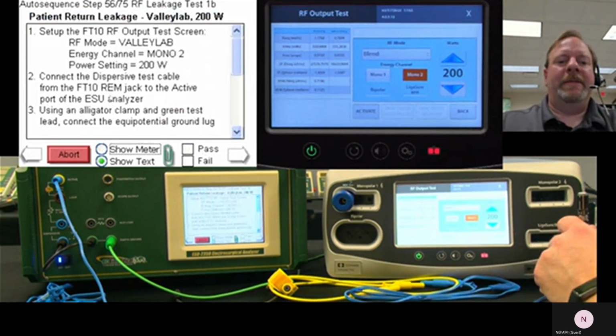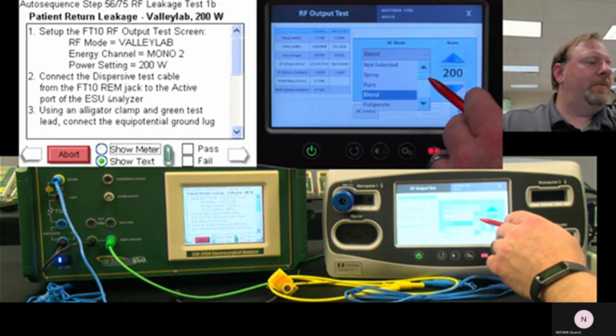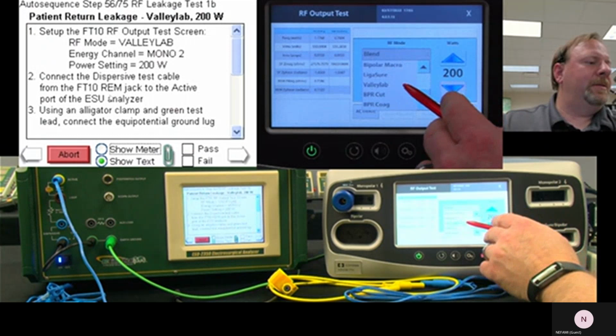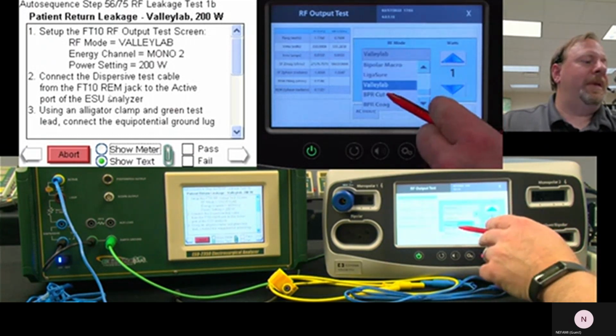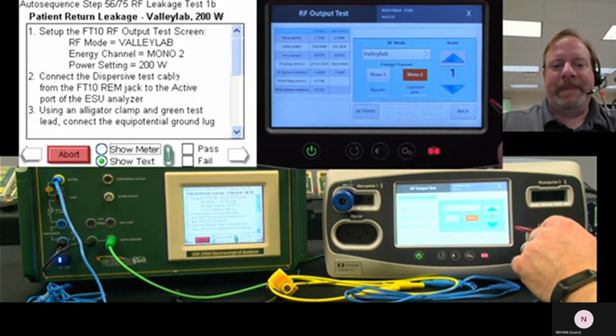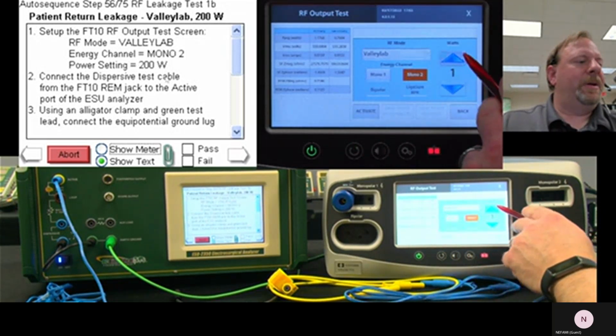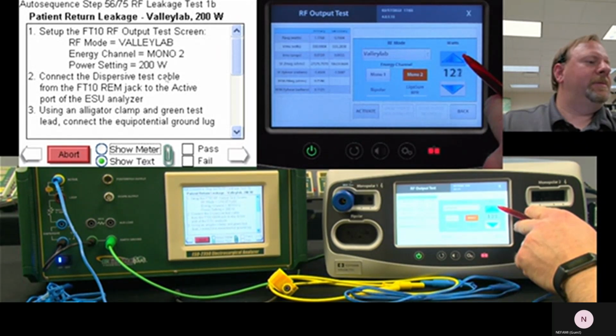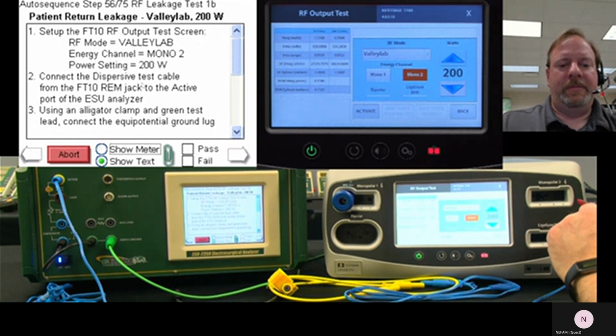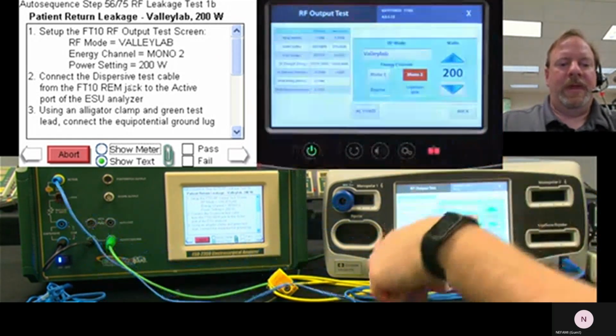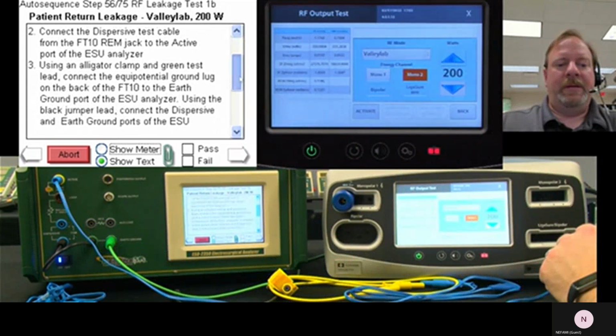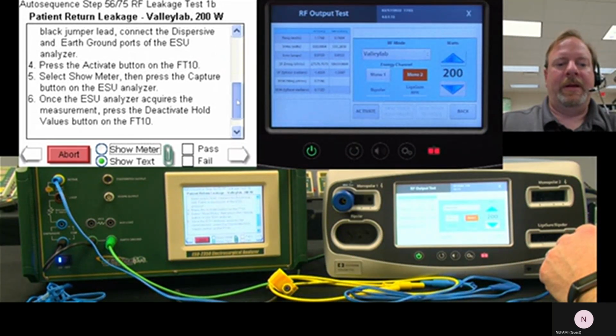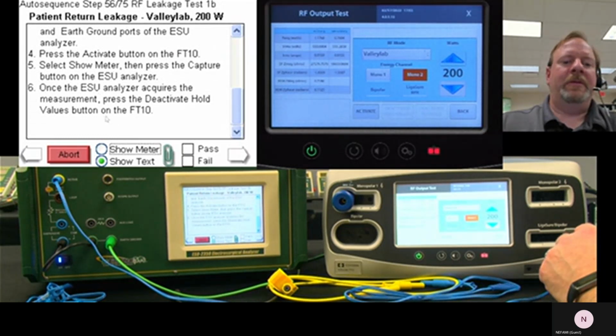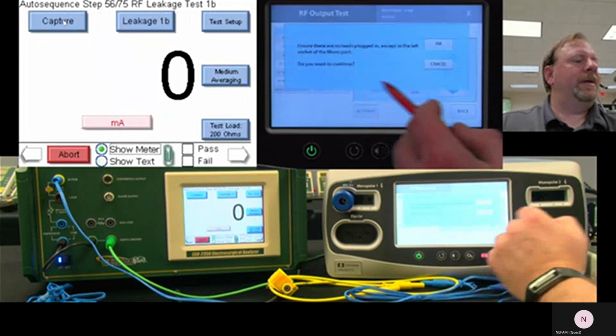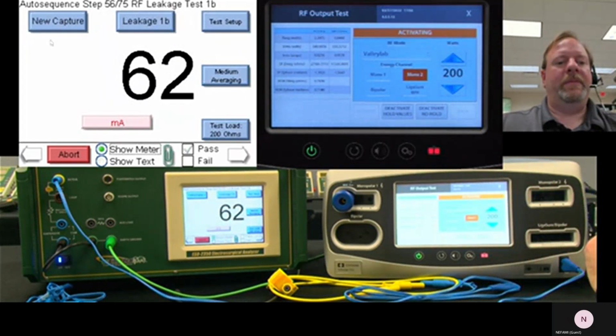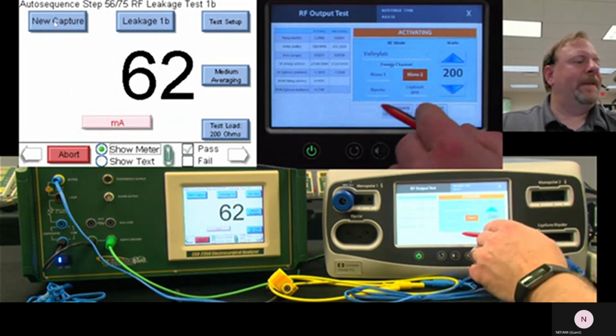Okay. Next step, Valley Lab mode. You would think that would be at the end, but it's not. It's right before the B for bipolar. Anyway, I digress. Monopolar 2, very good. 200 watts. There we go. Dispersive cable to the active port, still there. Ground lug, still there. Black lead, still there. Our connections are good. Press active, show meter, yes. Activate. Take our measurement. Deactivate.